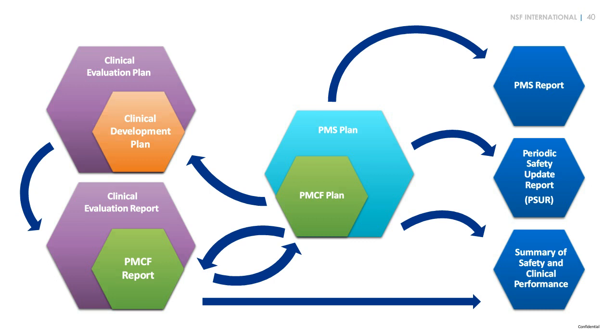These activities should also be considered in the clinical development plan, which is part of the clinical evaluation plan. The results and conclusions of the PMCF activities should be part of the clinical evaluation report, which in turn is also an input for the update of the PMCF plan.